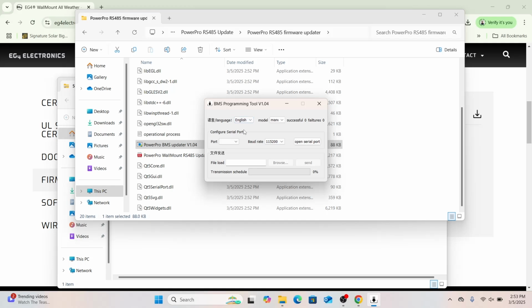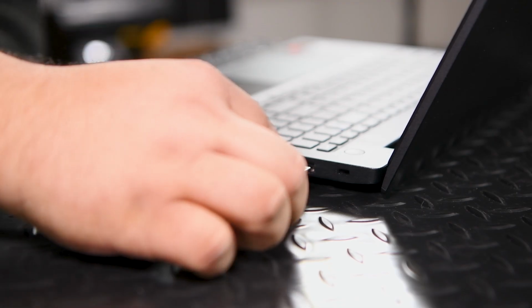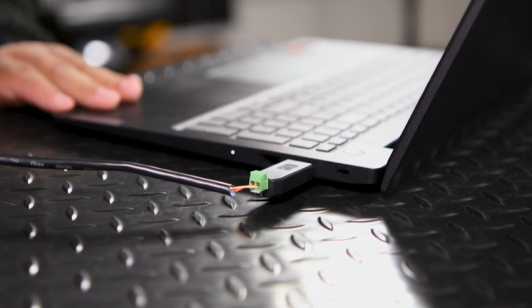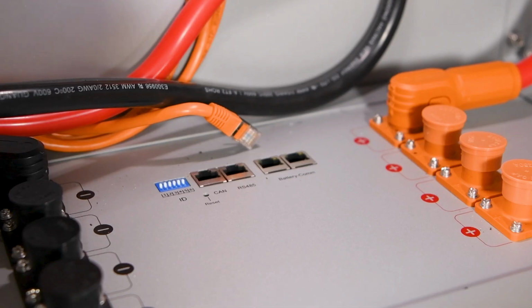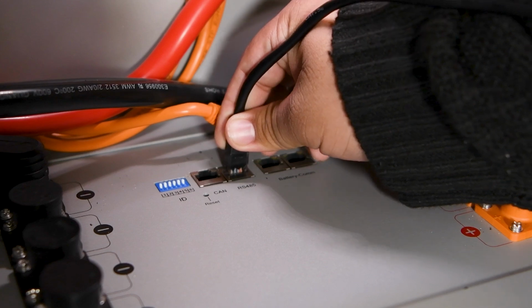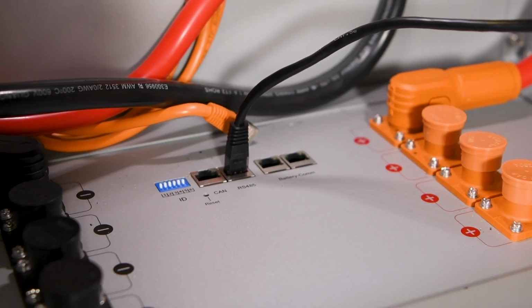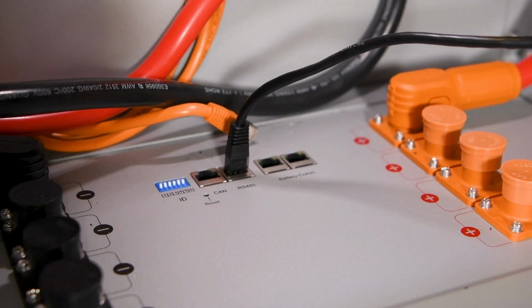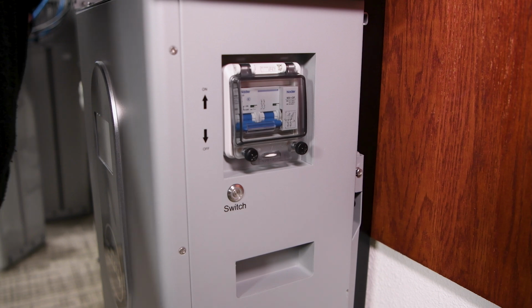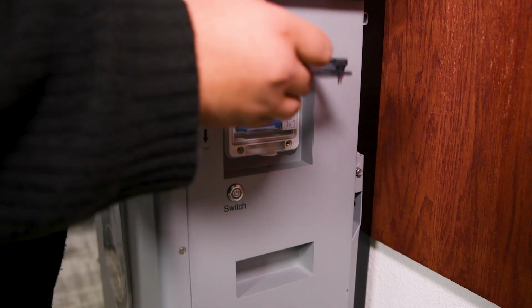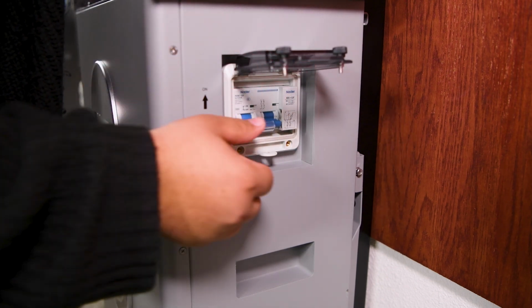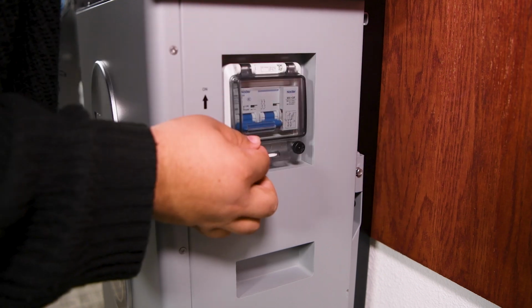Before continuing with the program, make sure you have your read-write cable plugged into the RS-485 port on the PowerPro battery. Then turn on your battery. You don't have to have the breaker on, since we don't want the battery charging or discharging during the update.